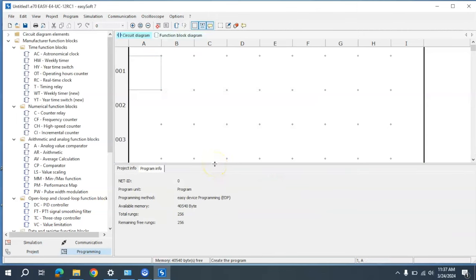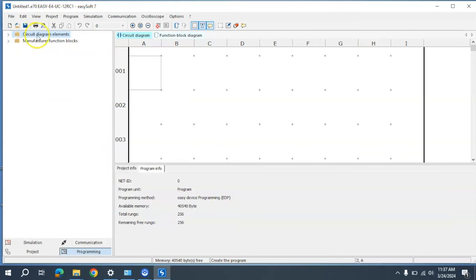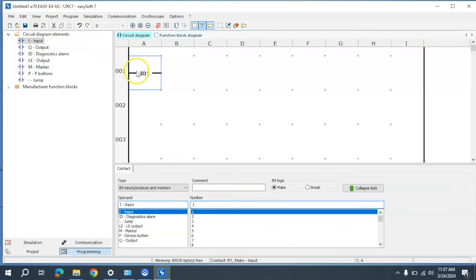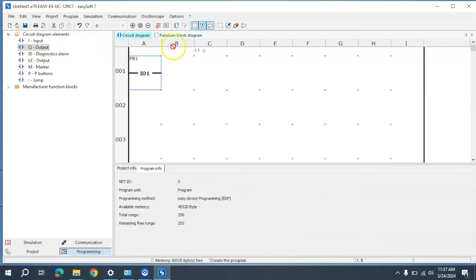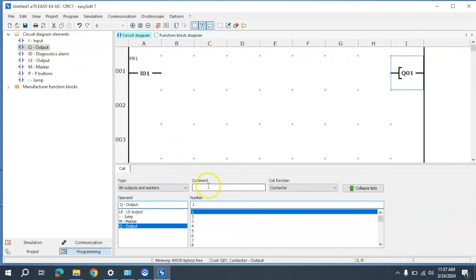I'm just going to show you how to input a very simple PLC program. We'll come up to circuit diagram elements and grab our input here. This is our input and I'll label it Push Button One — you can see the name appears here. You have the choice when you grab an input to make it a make or a break logic. We're going to make it a make, meaning it goes true when the switch is closed. Then we'll grab an output, which will be identified as Q1, and we'll call it Light One.